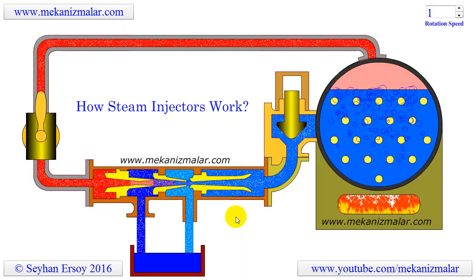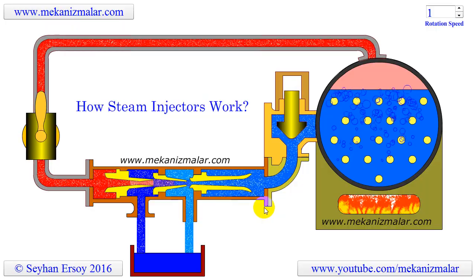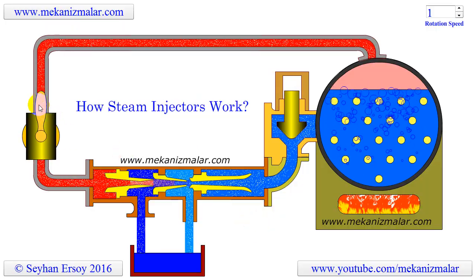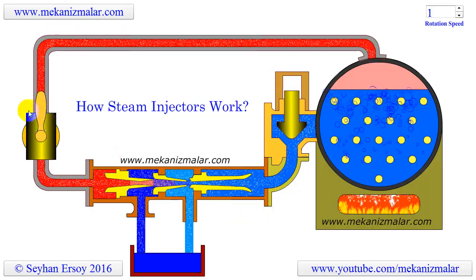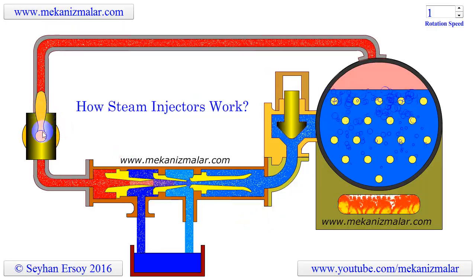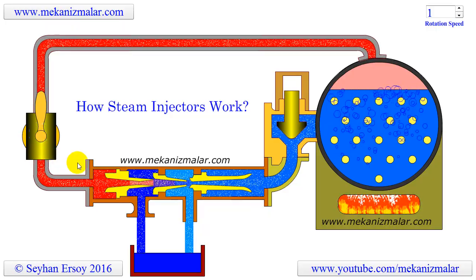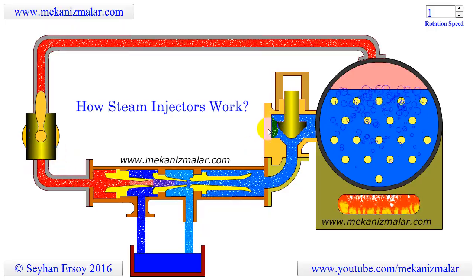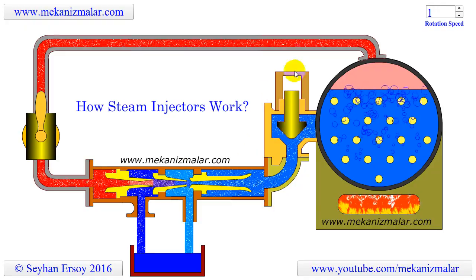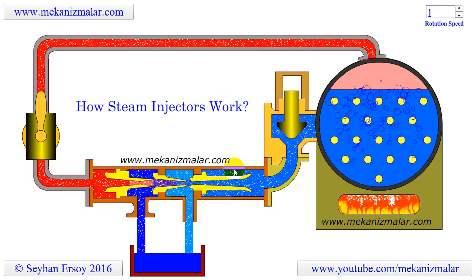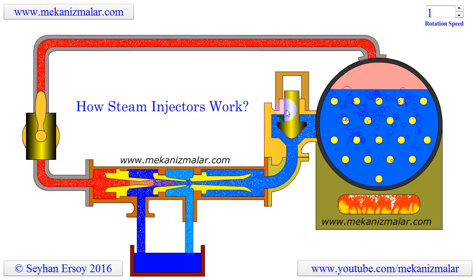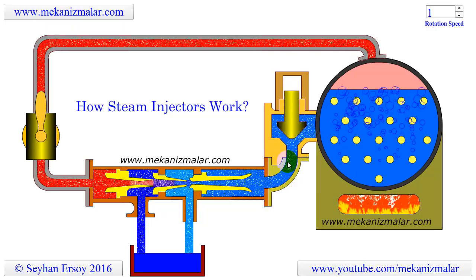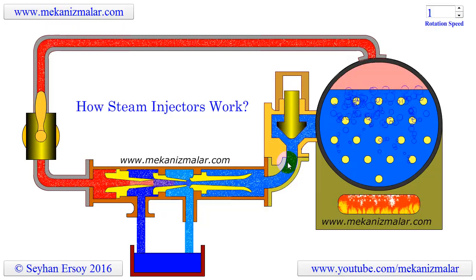The steam injector's operation can be interrupted by turning the valve manually or automatically off. This will cut the flow of steam to the injector, and in turn the water flow from the reservoir will stop. During this time, the check valve shown here will prevent the boiler water from escaping to the reservoir.